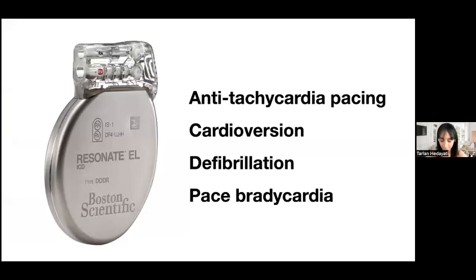Good question. Somebody asked, are the electrical voltages so small in internal pacing that the patient doesn't feel it, or do they feel it? So it depends on the patient. Some are very sensitive and can tell when their pacemaker is working, when it's online, and some don't. It's really dependent on the patient. The voltages are very low, but some people are just more in tune with their body and can tell when the pacemaker is working. We certainly cannot tell by touching the patient or listening, you're not going to be able to tell, but sometimes the patient can.